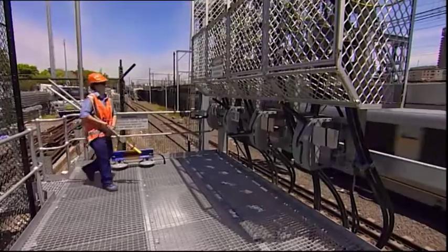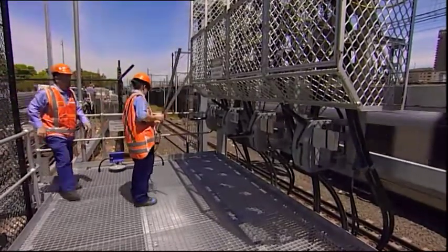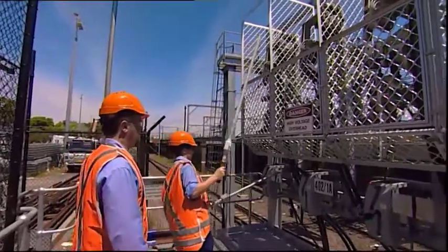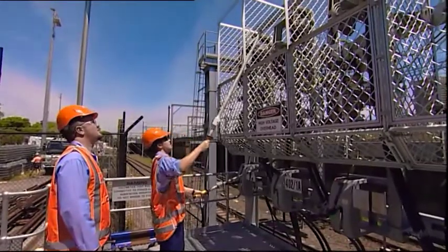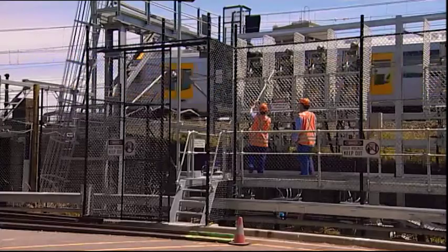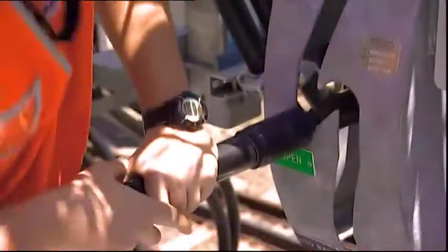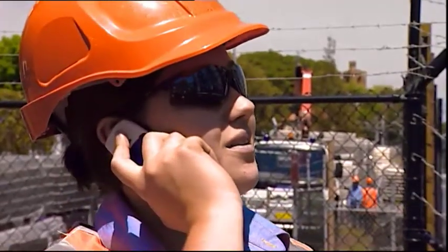The two long sticks were a 1500 volt tester. The first time I checked was to make sure the tester was working correctly. Then the second time was to make sure it was dead, that there was no voltage on that second switch, because that's what I was opening. Then you have to test the tester again to make sure it didn't break while testing. When the test is fine, then I'm able to open up the switch. I've opened the 1500 volt link.